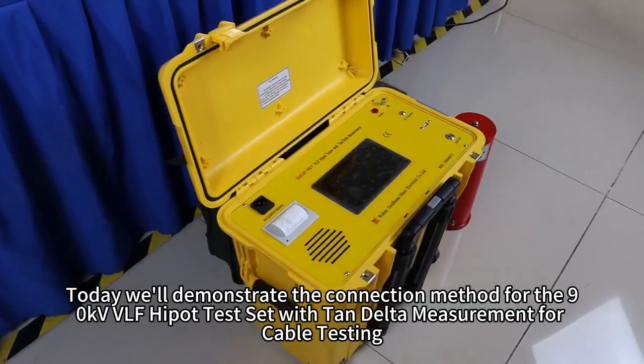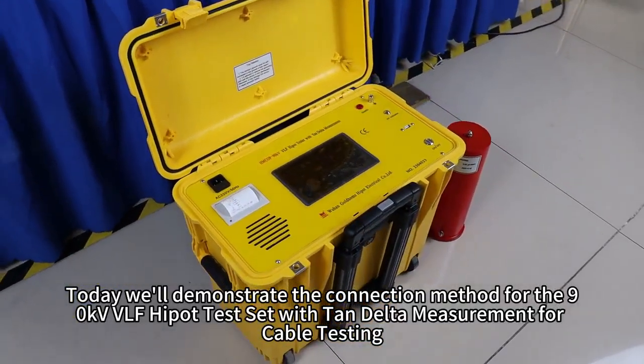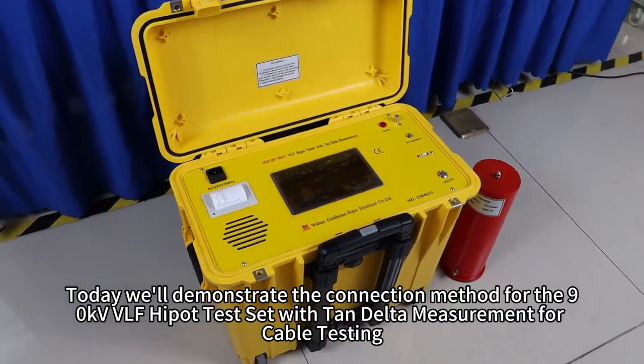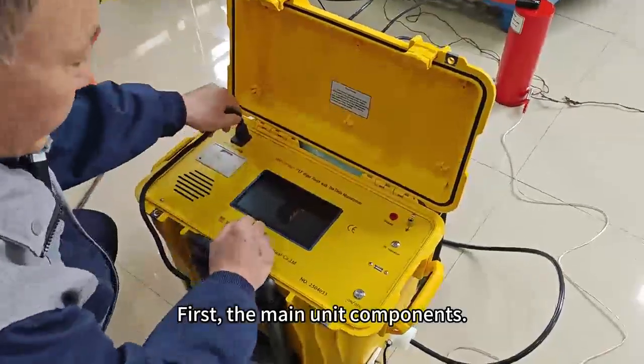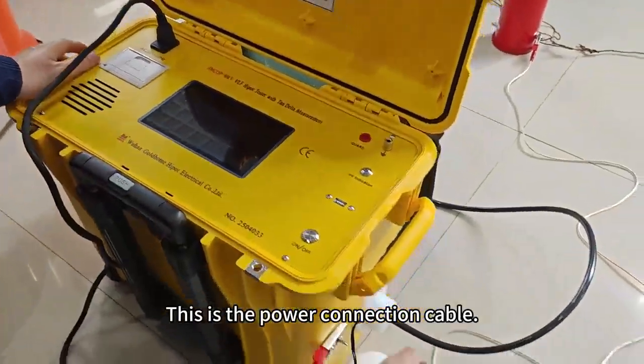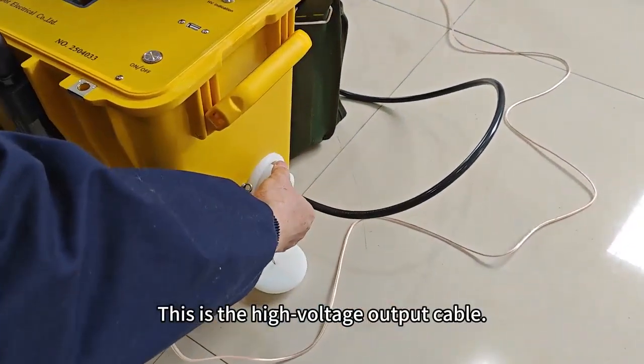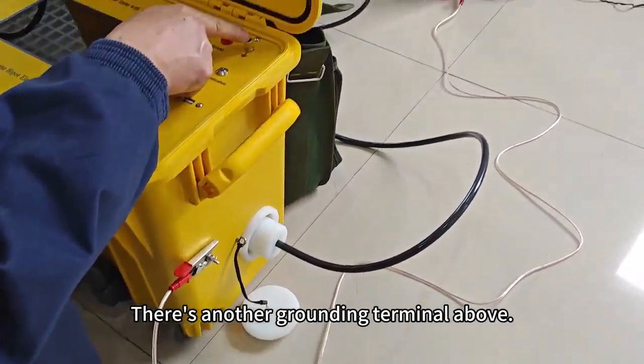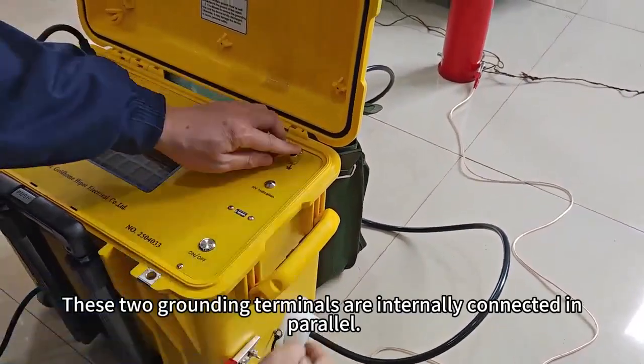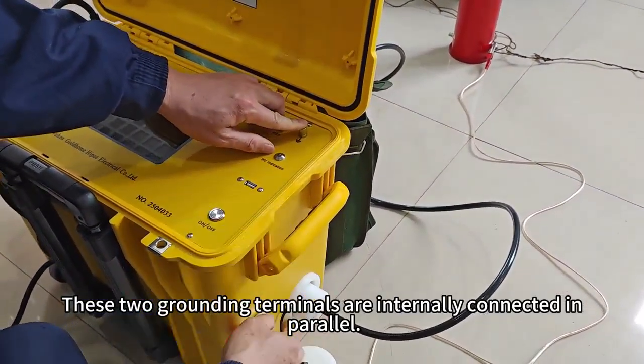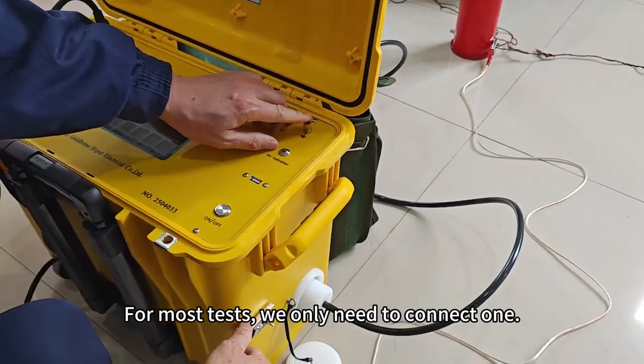Today we'll demonstrate the connection method for the 90 kV VLF Hipot test set with Tan Delta measurement for cable testing. First, the main unit components. This is the power connection cable. This is the high voltage output cable. This terminal is a grounding terminal. There's another grounding terminal above. These two grounding terminals are internally connected in parallel. For most tests, we only need to connect one.